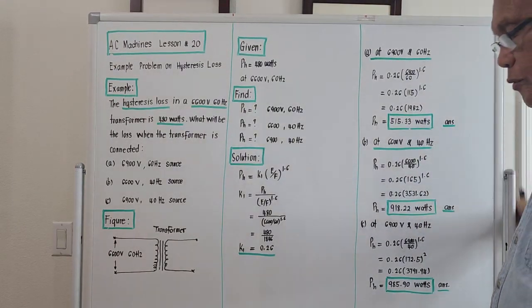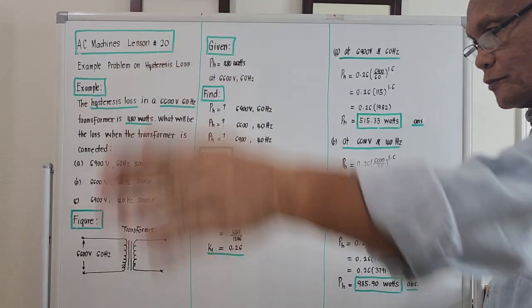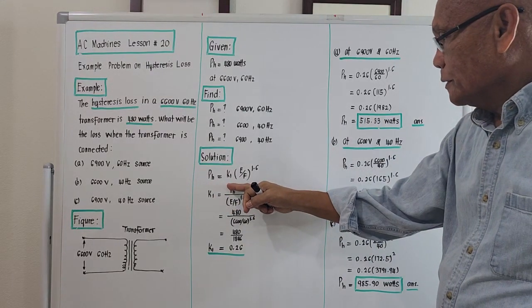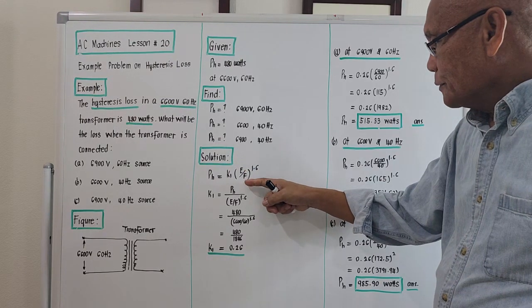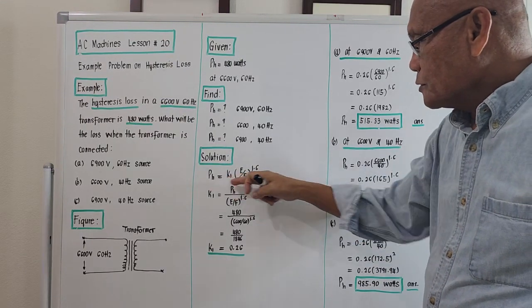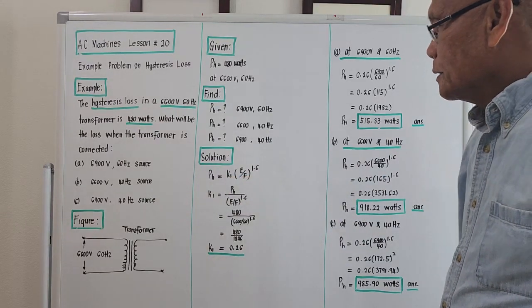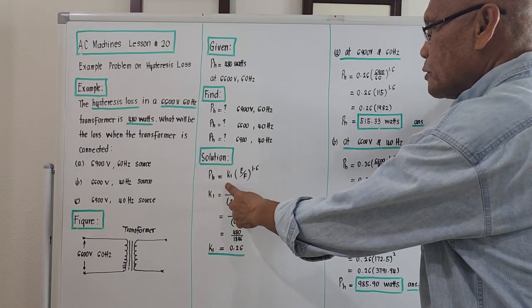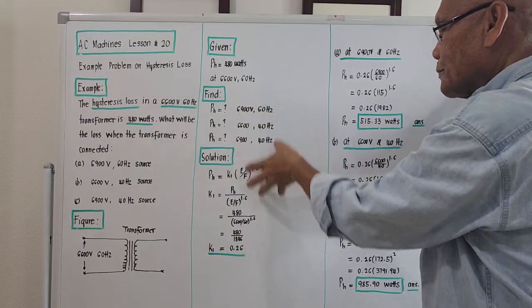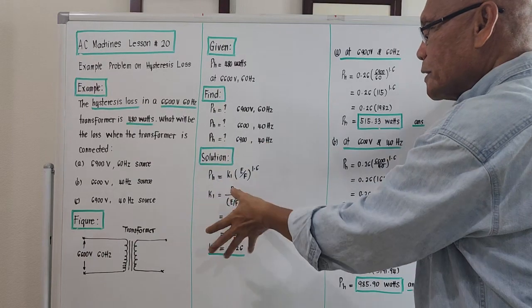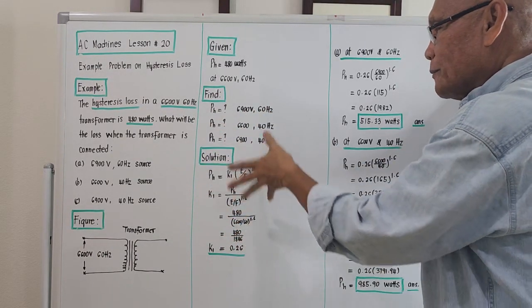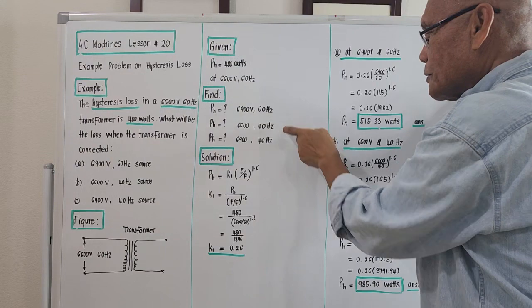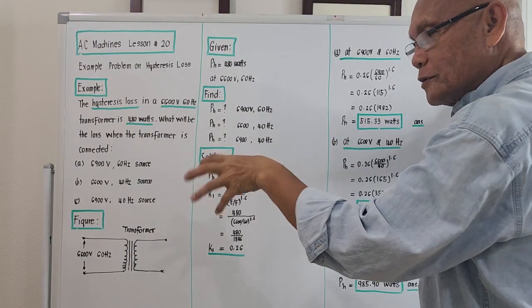To bring out the solution, we will be using the derived equation from previous lessons. For hysteresis loss, it is actually a certain constant k1 times the ratio E over f — where f is frequency — raised to 1.6. This is an exponential equation. The key to the solution is that we must compute for k1 first. When we go to the variations at different voltages and frequencies, we know the value of k1 because we are talking of the same transformer.